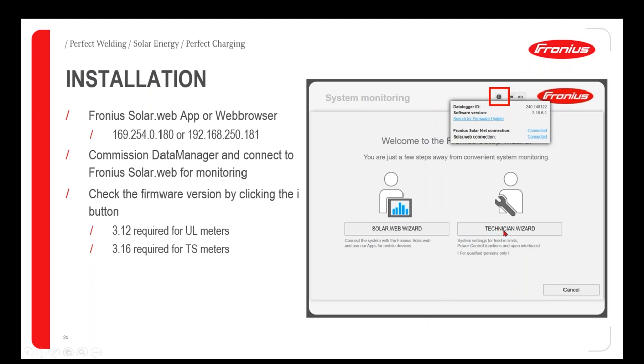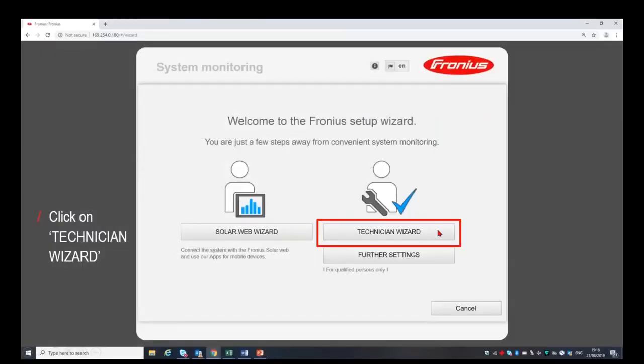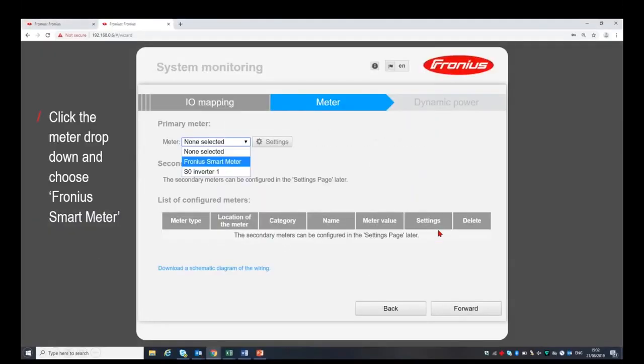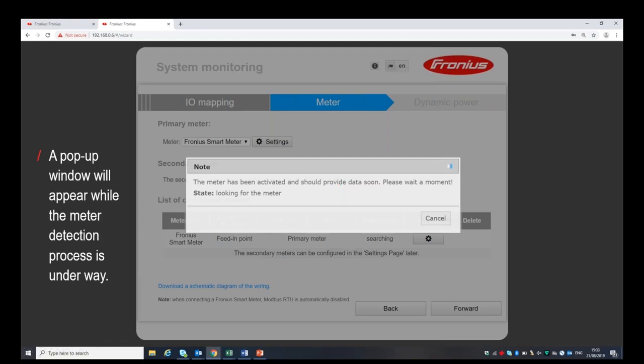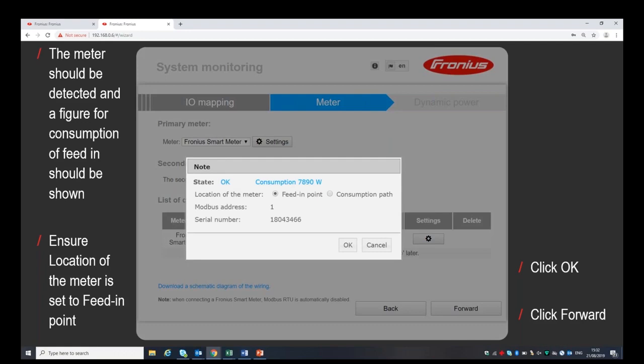So let's click on the technician wizard and we'll go through the process. A number of the pages are very similar on the technician wizard to the SolarWeb wizard until you get to the meter setup page. The first thing you want to do is to click on the meter drop-down and choose your Fronius smart meter. Once you've done that, click on settings. The device will now search for that smart meter, and hopefully you should see the status is okay, and you'll see a consumption reading for that smart meter. Make sure that it's set for the feed-in point. This just means that the meter is located where you're potentially feeding energy back to the grid.